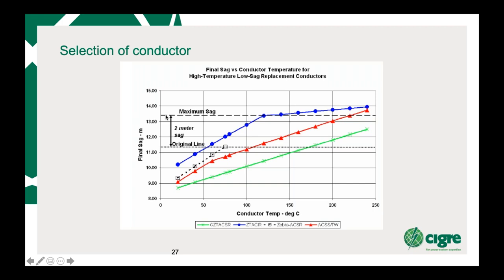So you've got a maximum sag at that point there, which will hit the regulation above ground. And now you need, in fact, from your current, to have around 200 degrees C for your conductor. In other words, it was a small conductor and we need to run it hot. What conductor types do we use?